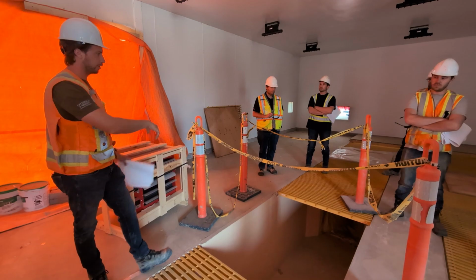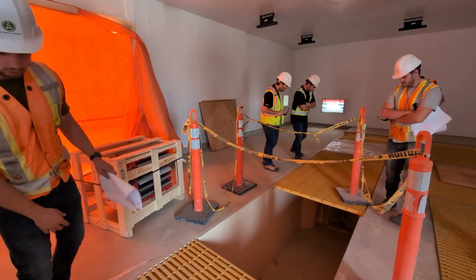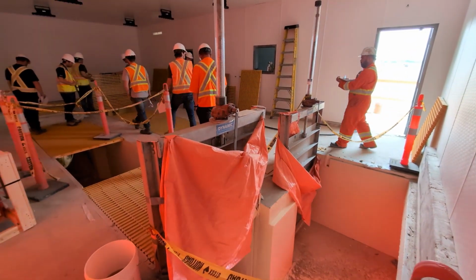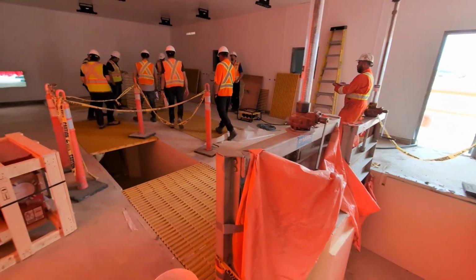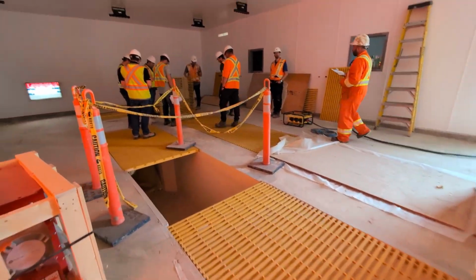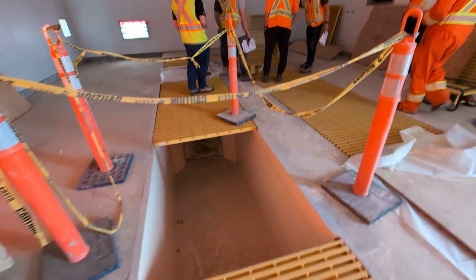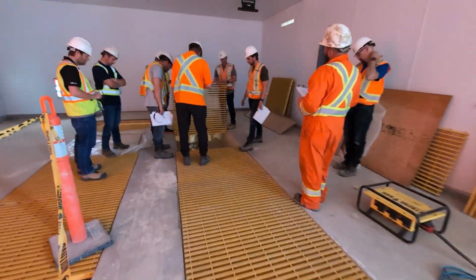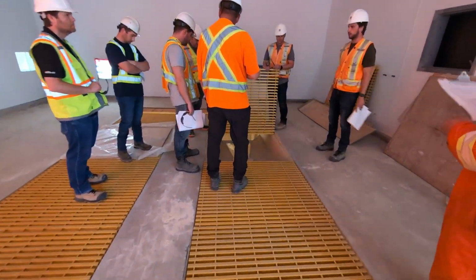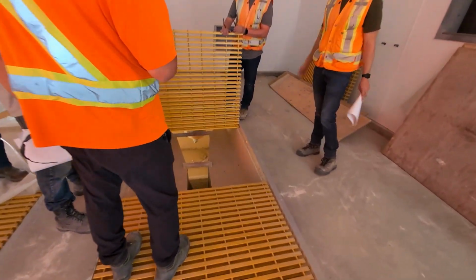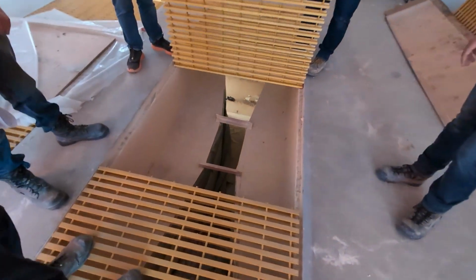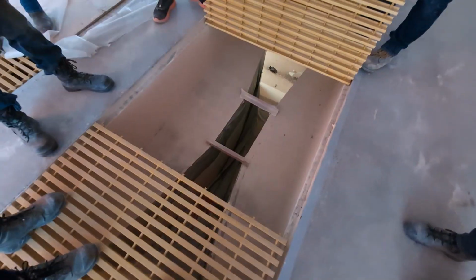Both of them get metered. I don't know if you can see it to the grade - if you look from over here, it gets a level sensor over it. There'll be a level sensor suspended at a point somewhere back here. It reads the level and follows formulas to turn that into a flow. So both channels, whether you're in your primary or your bypass, are both getting metered, and we'll have total flow coming through. Both get screened.